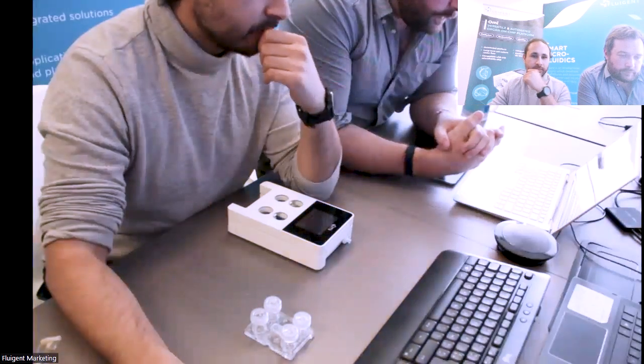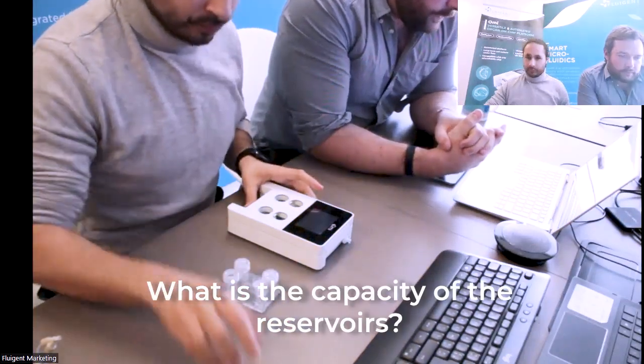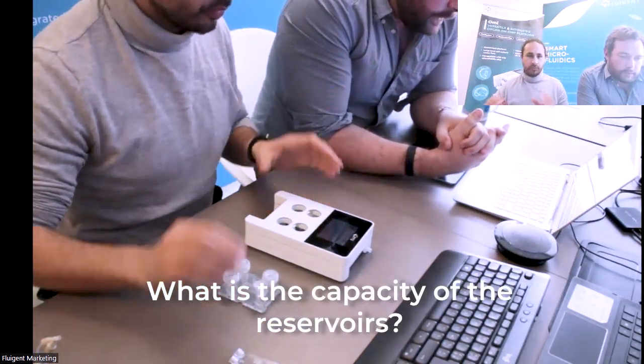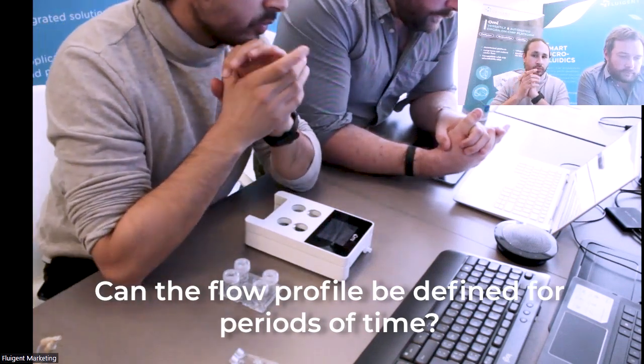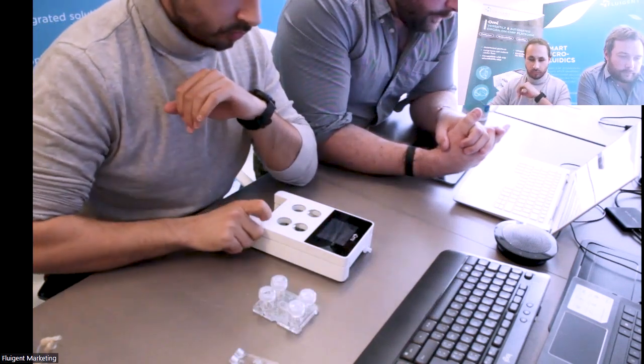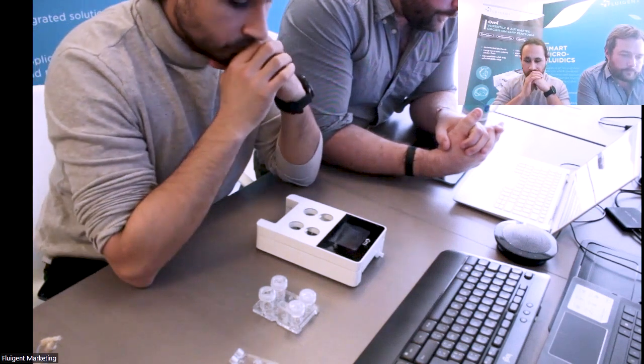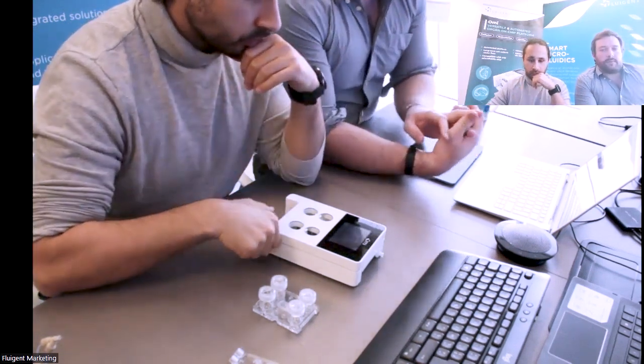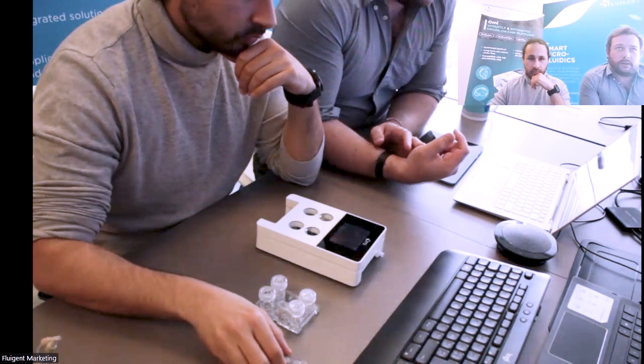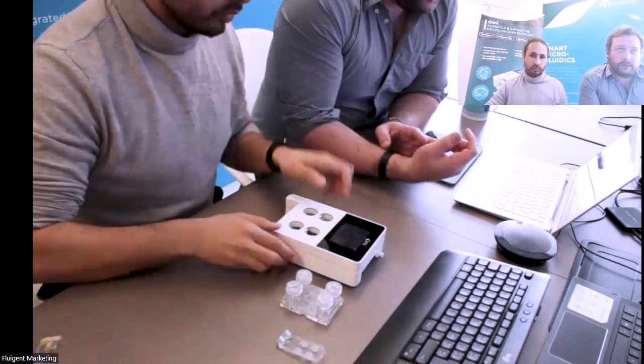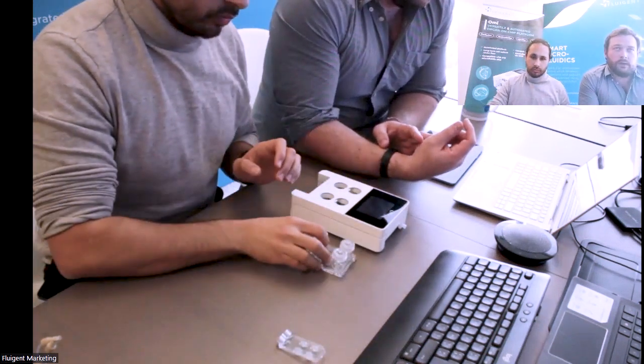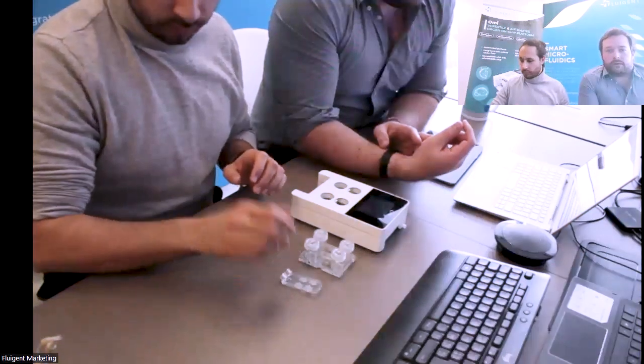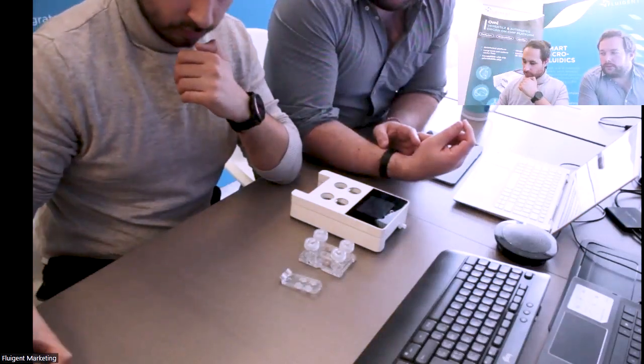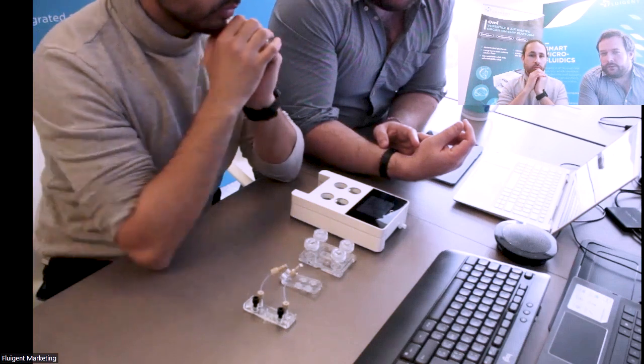So there is another question on the capacity of the reservoirs, and whether the flow profile can be defined for periods of time. The capacity of the reservoirs is a maximum of 4 milliliters, and the reservoir will be considered at low level if it's around 1 milliliter.